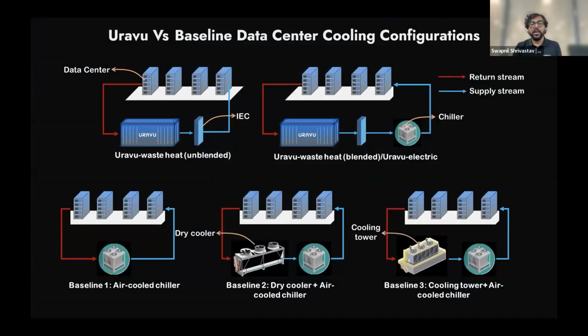The way we look at it, we don't have to intervene in a way that changes anything, but all your return loops can first be interfaced with our hardware. And the beauty of the hardware is that it works around a flexible load architecture. On one side you have facility water, which is a liquid, and on our machine side we also have a liquid salt. So it can modulate its flow rate and heat rejection based on the variable load coming from the data center. And we monitor 25 plus parameters in real time, including absorption of water, water production, flow rates, etc., to give you a very high efficiency solution.